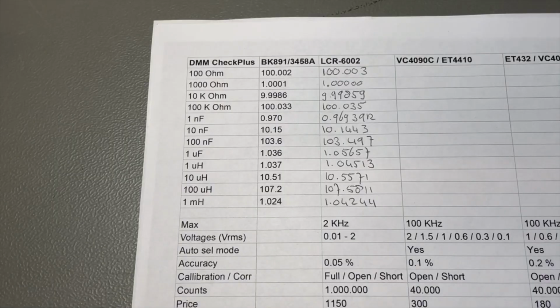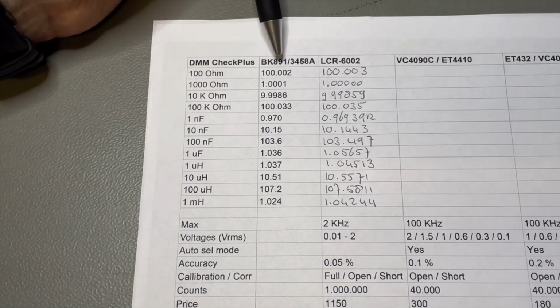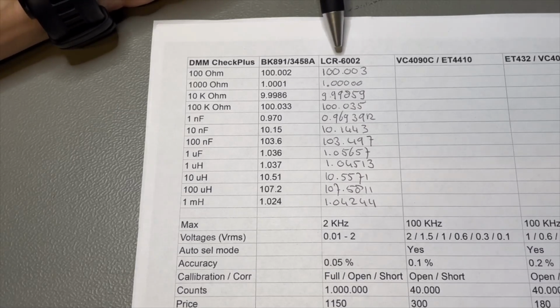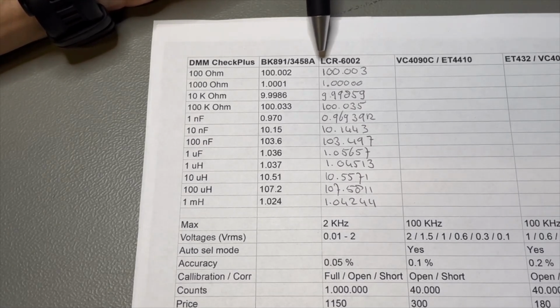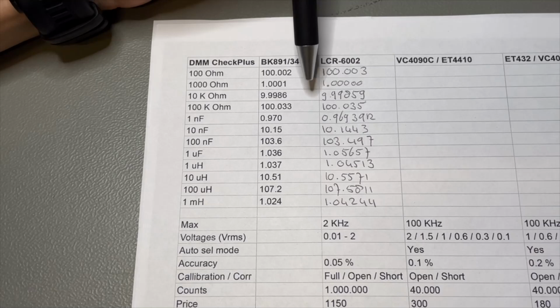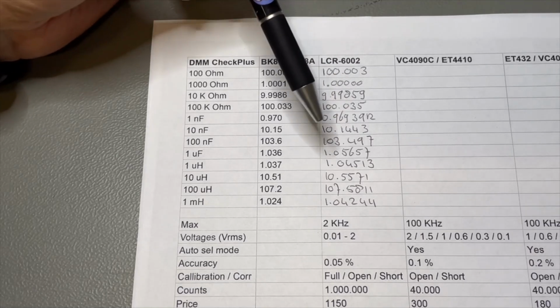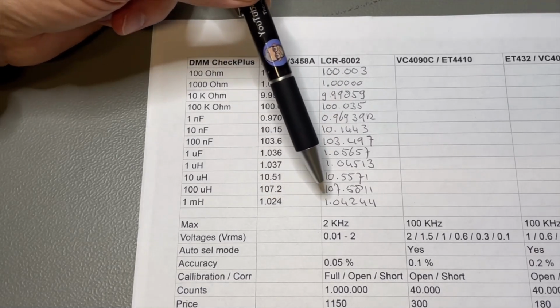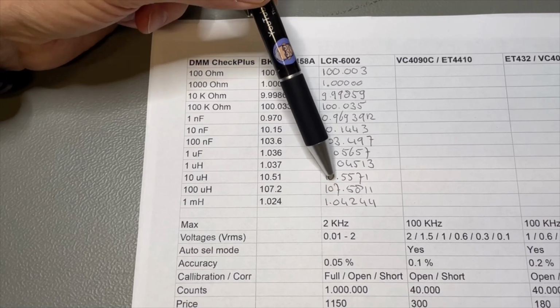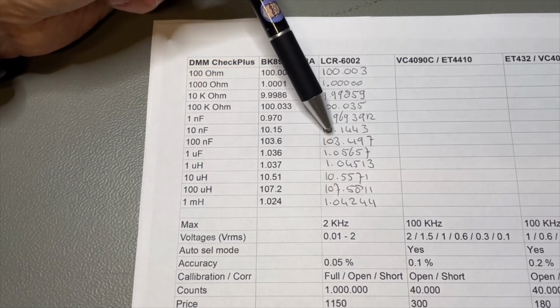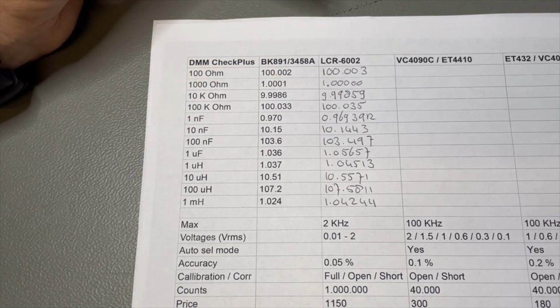Just to check our baseline, the measurements that DMM Check Plus did on their meters here, does that properly compare to our measurements that we did with a high precision LCR meter? And I would say they agree almost on the digit. Little difference here when it becomes a little bit bigger, but most of them are exactly the same. So this is a good baseline.